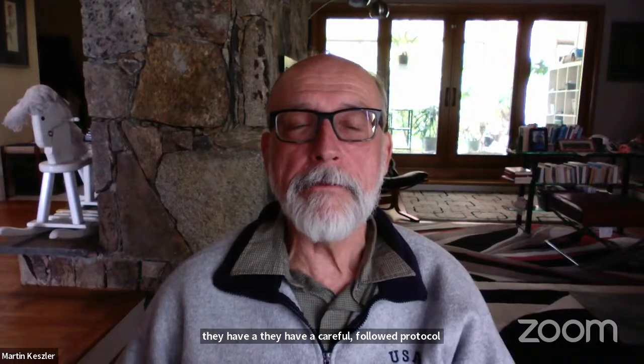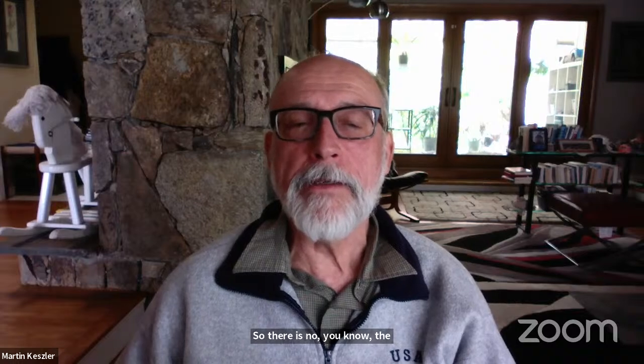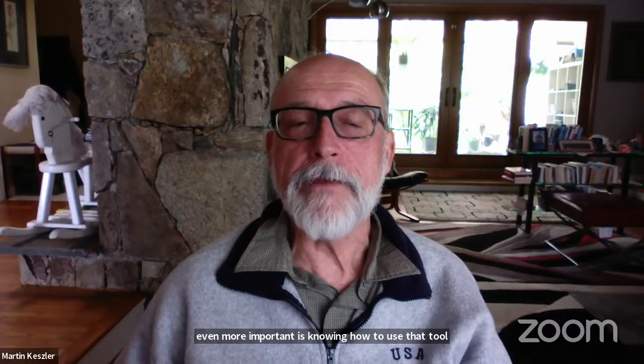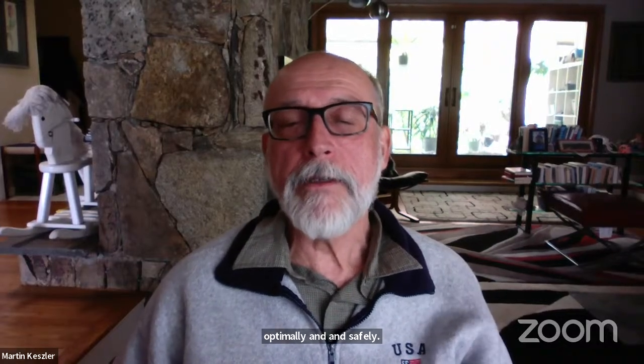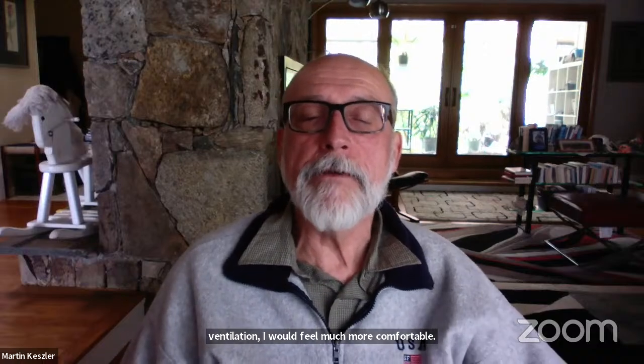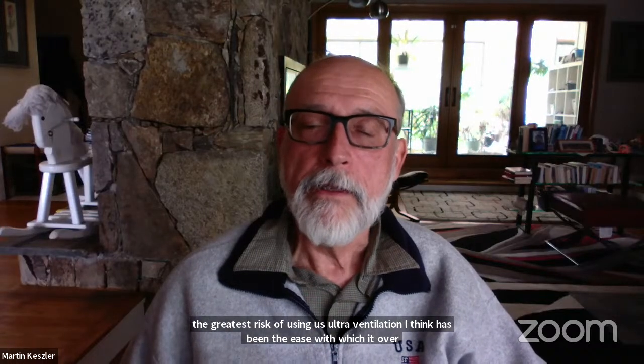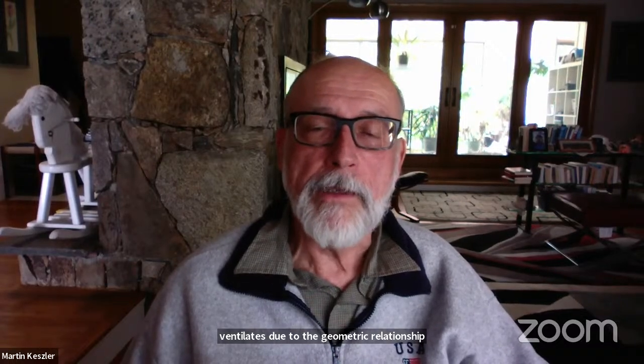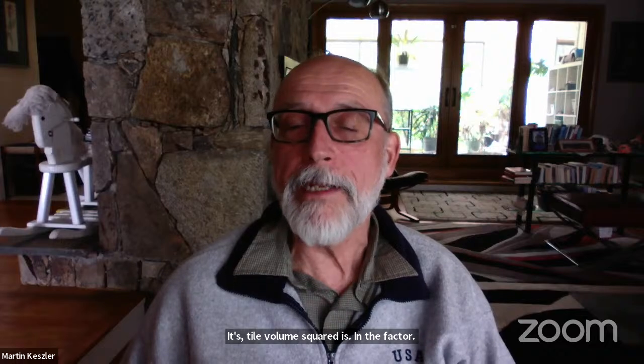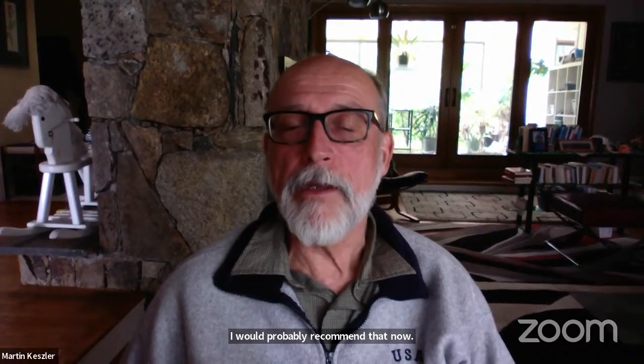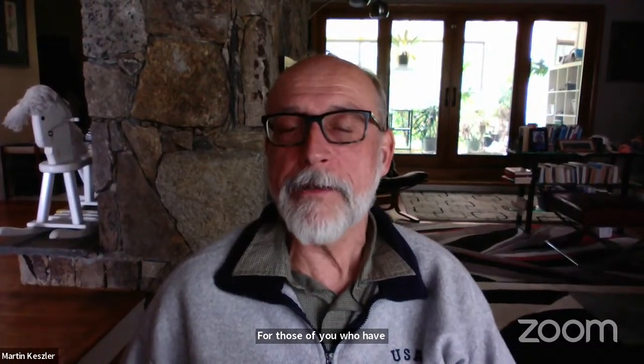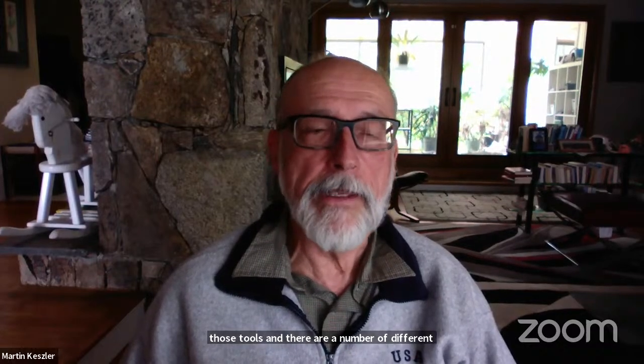So the tools are important, but even more important is knowing how to use that tool optimally and safely. So with volume targeted high frequency ventilation, I would feel much more comfortable recommending high frequency oscillatory ventilation with volume guarantee as a first line approach, because the greatest risk of using oscillatory ventilation, I think, has been the ease with which it overventilates due to the geometric relationship between tidal volume and CO2, right? It's tidal volume squared that is the factor. So yes, I would probably recommend that now for those of you who have the availability of those tools. And there are a number of different ventilators. The Draeger is not the only one that has HFOV with volume targeting.